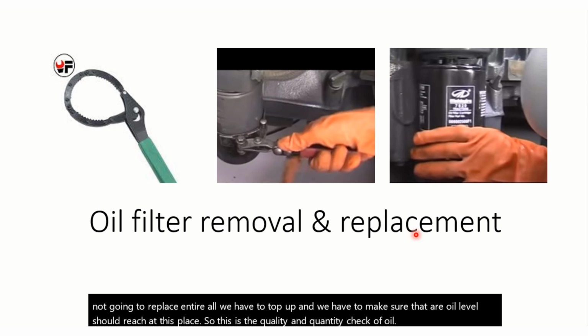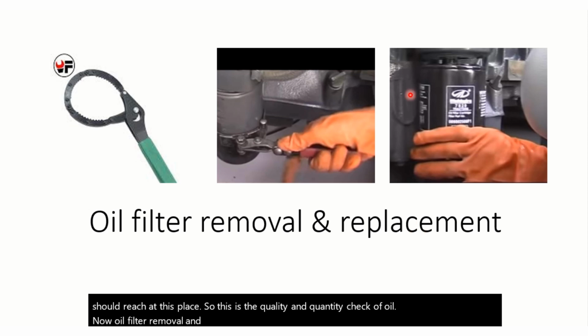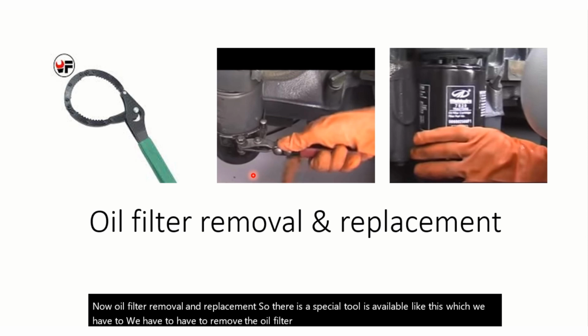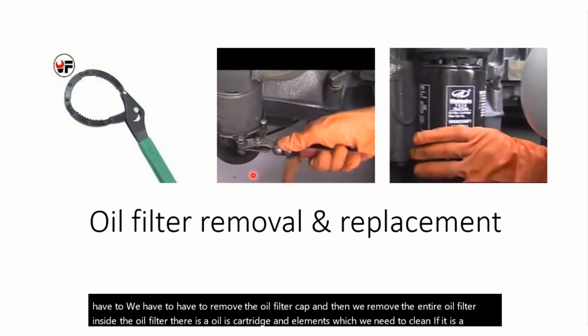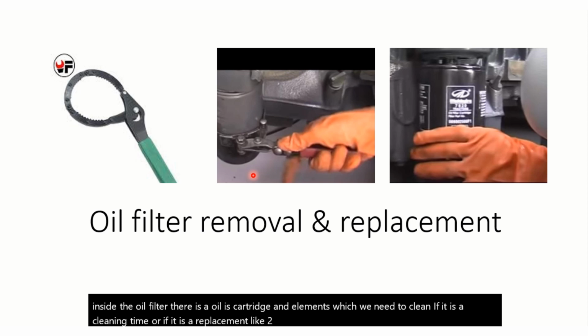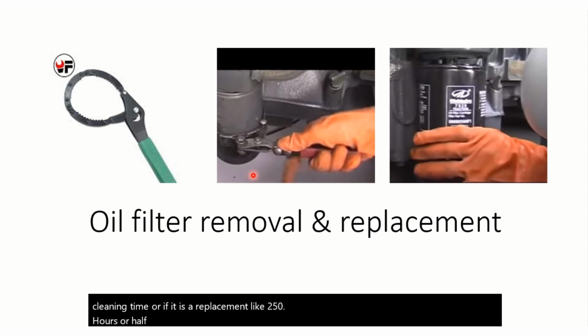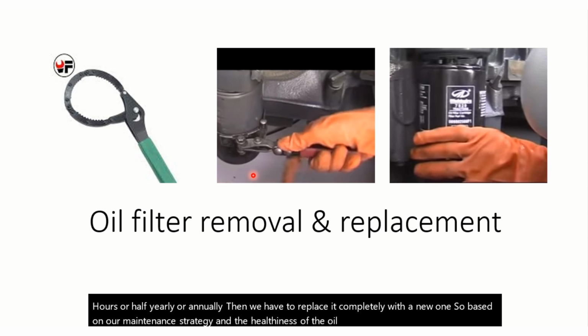Now, oil filter removal and replacement. There is a special tool available like this, with which we remove the oil filter cap, and then we remove the entire oil filter. Inside the oil filter there are oil cartridges and elements which we need to clean if it is cleaning time, or if it is a replacement, like 250 hours or half yearly or annually, then we have to replace it completely with a new one. So based on our maintenance strategy and the healthiness of the oil filter, we have to decide whether we are going to replace it or clean it.